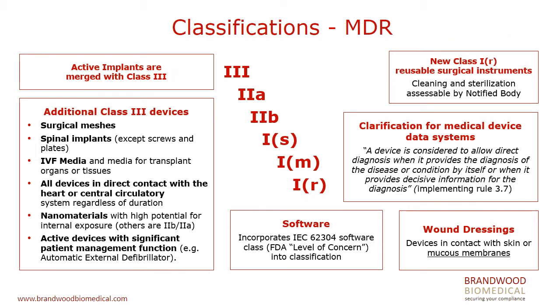There's a new class one subset. We're well aware of class one sterile and class one measuring function devices. Now we have a class one R, reusable surgical instruments. Those devices, surgical instruments which are intended to be reusable, will now require review of conformity assessment by a notified body with specific focus on cleaning and sterilization only. In other words, not a complete review, but the notified body will need to look at the validation of cleaning and sterilization for reusable surgical instruments.